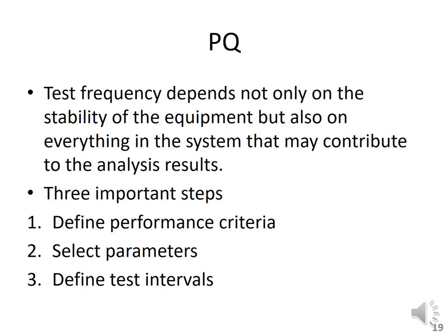And then third, define the test intervals. So when the test is required to be performed, or when the test should be performed, you have to define the test intervals, that after this much time the performance qualification tests should be performed. So these three steps are very important. These three factors are very important with reference to the performance qualification.